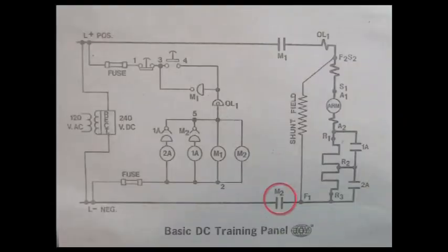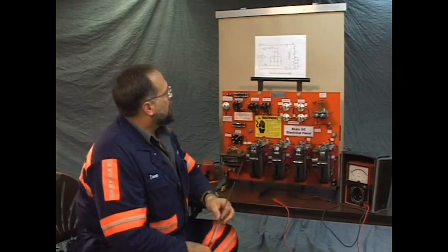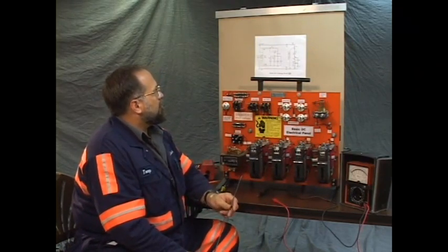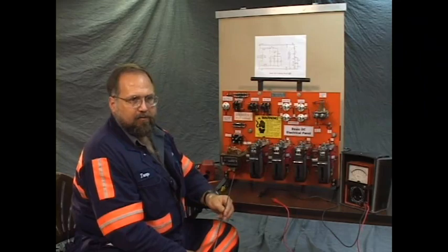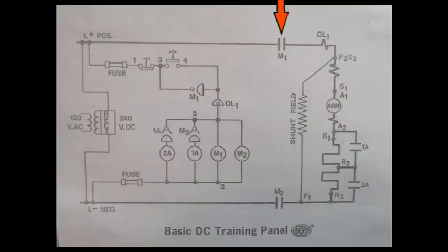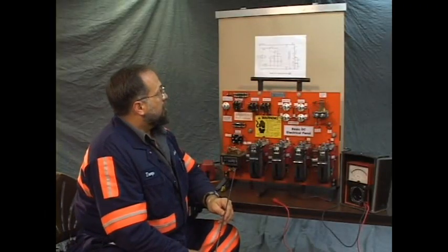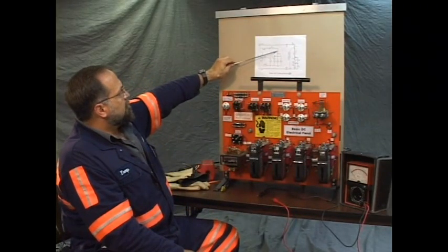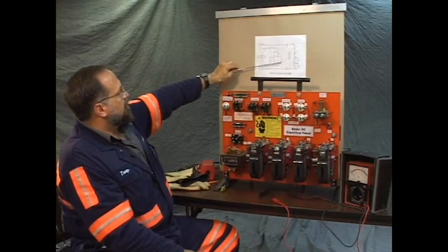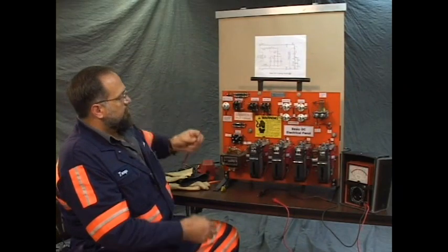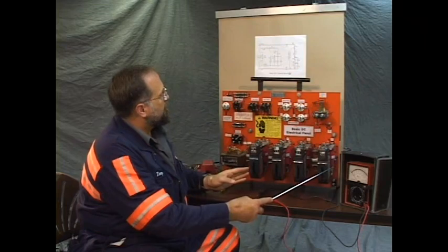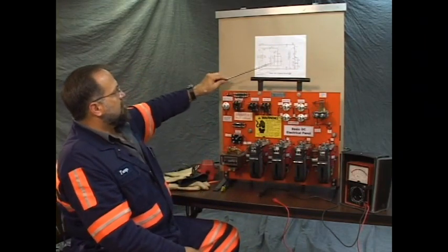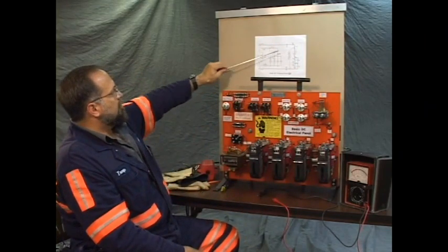The M2 contactor, that's this one. The M1 and M2 are commonly referred to as master contactors. As you can see, the M1 is on the positive side of the circuit. It's thought of as the positive contactor, and the M2 is the negative contactor. And they close simultaneously. As you can see, when the control power is applied, M1 and M2 close at the same time. These two go in at the same time. One provides a connection for the motor to negative, the other one to positive.